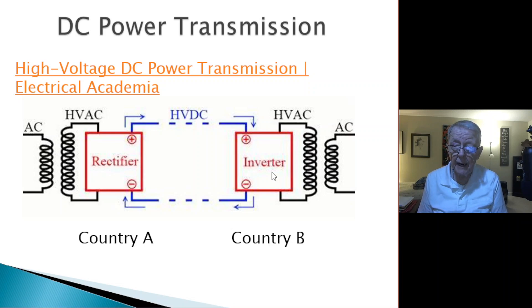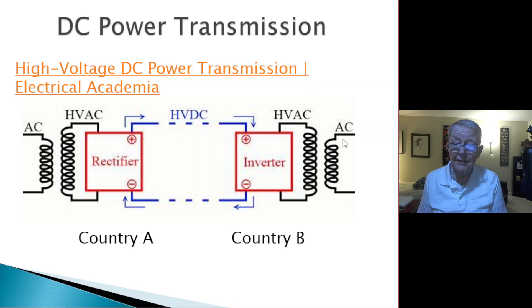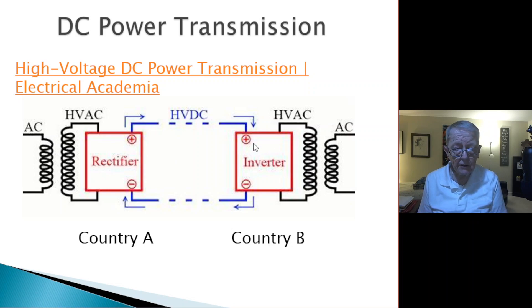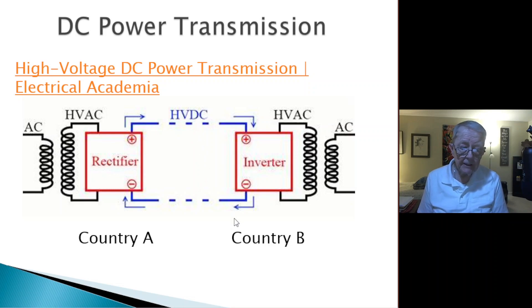This comes in handy in Europe, where a small country B wants to borrow electricity from country A. They both have 50-cycle AC, but they're not necessarily in phase, so you can use DC transmission to resynchronize — take the DC and sync it with the local AC. However, it's quite power-hungry: there are losses in the transformer, loss in the passive rectifier, and the inverter takes energy to convert DC back to AC, plus power loss in the high-current transmission line.